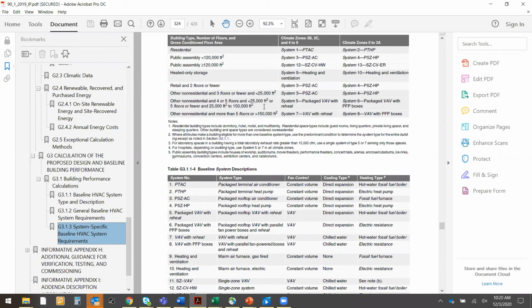I think I'm going to rephrase what you just said, Gail, because I think you're onto something. If you are greater than 25,000 square feet and your proposed and baseline are package single zone, you're restricted there. If you're less than 25,000 square feet and your baseline is package single zone, but your building chooses to do VAV, I think you should be able to take credit for that. I can come up with a percentage threshold there to say, okay, maybe the model will spit out a package single zone, but I get an X% allowance because I have a VAV system and not a constant volume system in my proposed. Because I feel like we're penalizing people a little bit for doing something better.